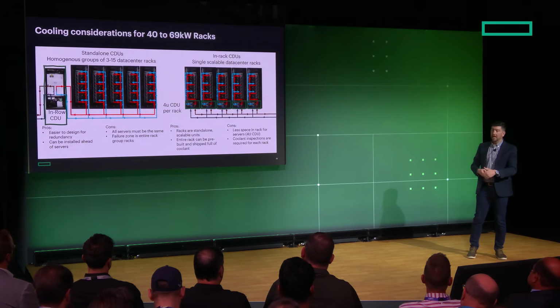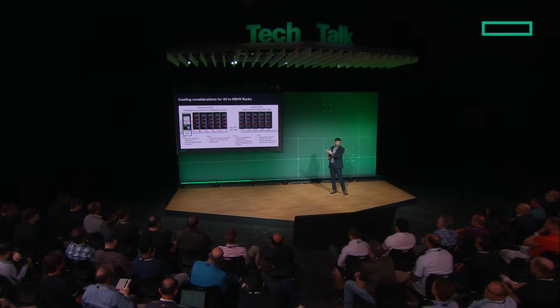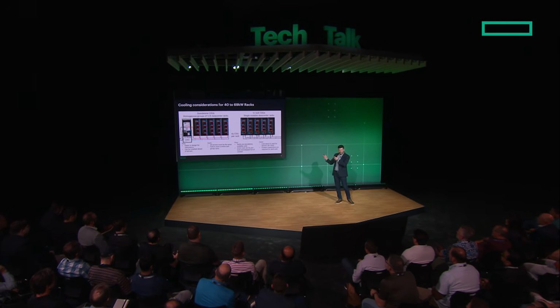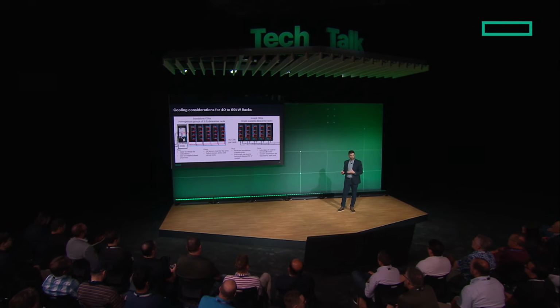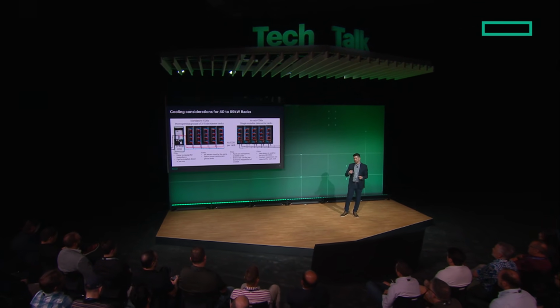But the downside is the CDUs often can't tell the difference between what's in these racks. So if you have a big, hungry GPU rack that needs a lot of flow, beside a CPU rack running on idle, the big CDU might overcool some racks and undercool others, unless you're doing a lot of manual flow-setter valves. That's kind of the main difference between these two.